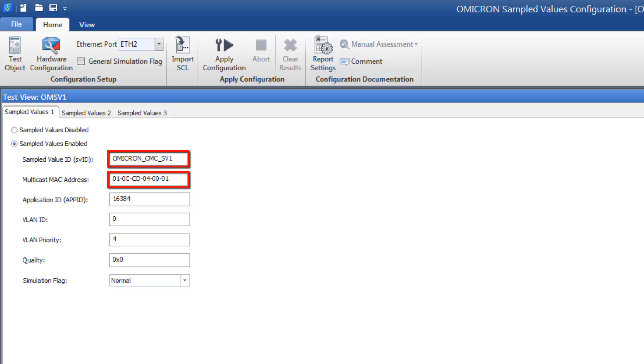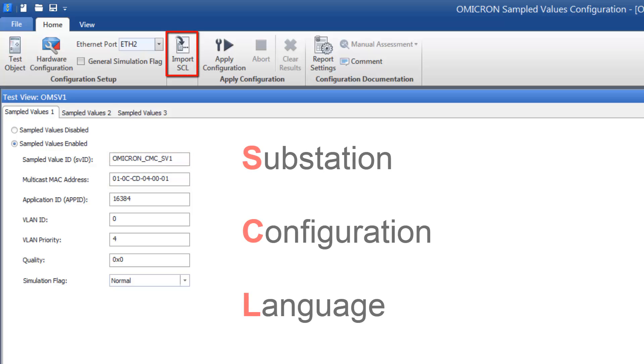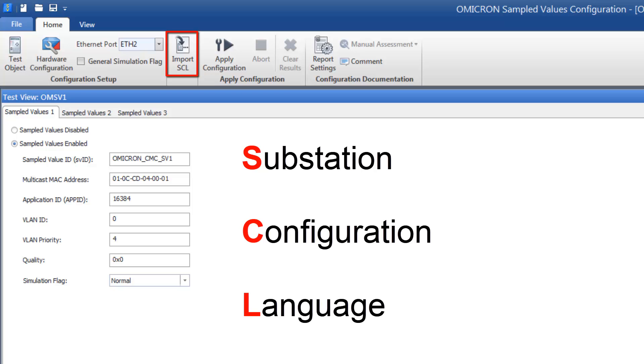For a test, it is very important to set the right values here, otherwise a relay will not find its stream on the network. You can also import these values from an SCL file, just like in the Goose Configuration module.